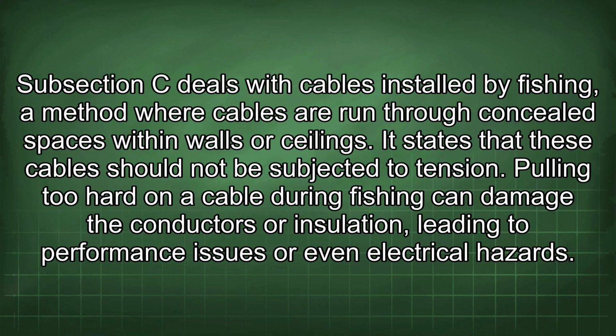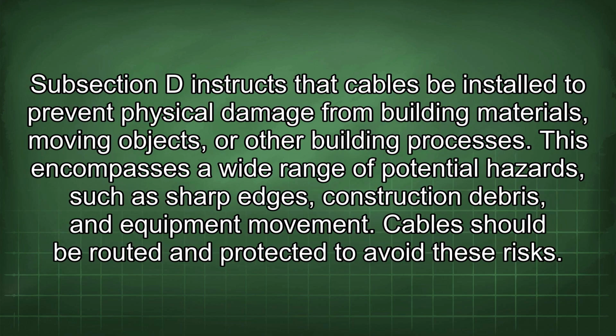Subsection C deals with cables installed by fishing, a method where cables are run through concealed spaces within walls or ceilings. It states that these cables should not be subjected to tension. Pulling too hard on a cable during fishing can damage the conductors or insulation, leading to performance issues or even electrical hazards. Subsection D instructs that cables be installed to prevent physical damage from building materials, moving objects, or other building processes. This encompasses a wide range of potential hazards such as sharp edges, construction debris, and equipment movement. Cables should be routed and protected to avoid these risks.